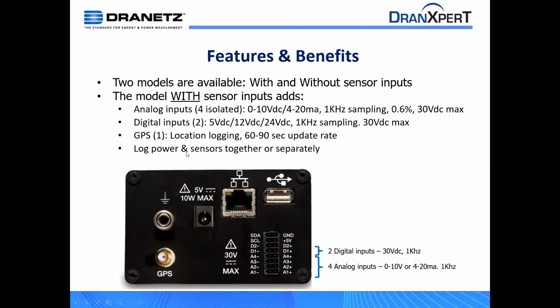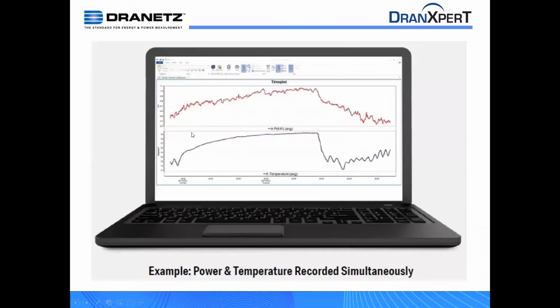So an important point is you can log on DranXperT only power, only the sensors and transducers, or together. So you could do one, the other, or both simultaneously. It's your choice. One doesn't require the other. And what that allows you to do, and you can see here just a simple trend, this is your power and this is your temperature. And you can see them within DranView software. They're trended right at the same time. So you can see the direct relationship between your power consumption and your temperature in this particular example. And again, the temperature can be replaced with any sensor or transducer type output that may be available to you, as long as it's a 10 volt output or 4 to 20 milliamp output.